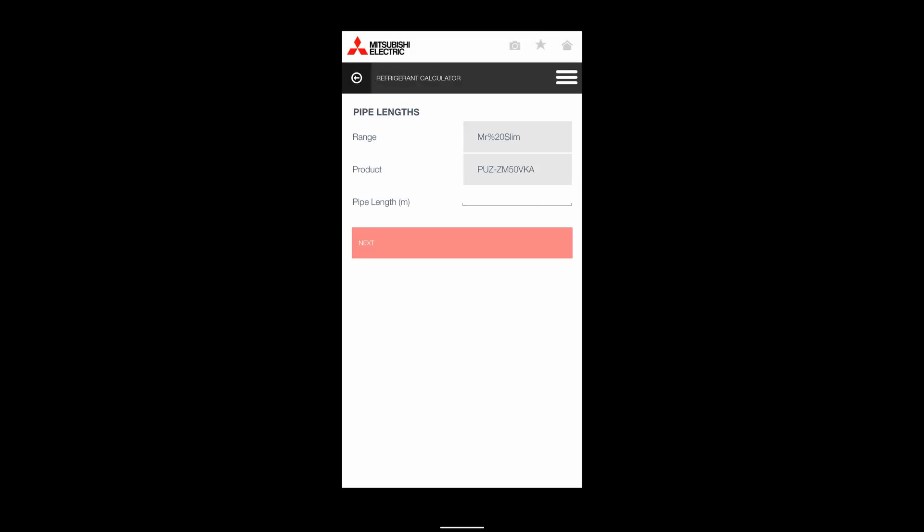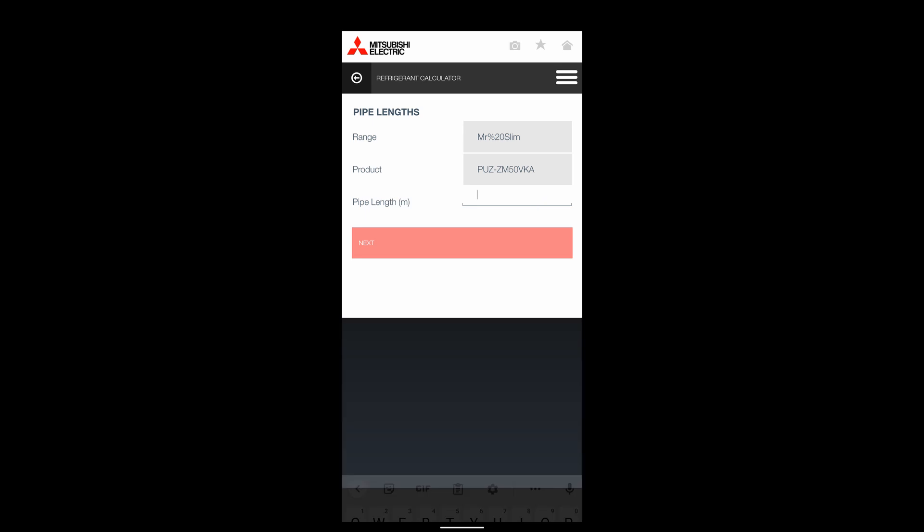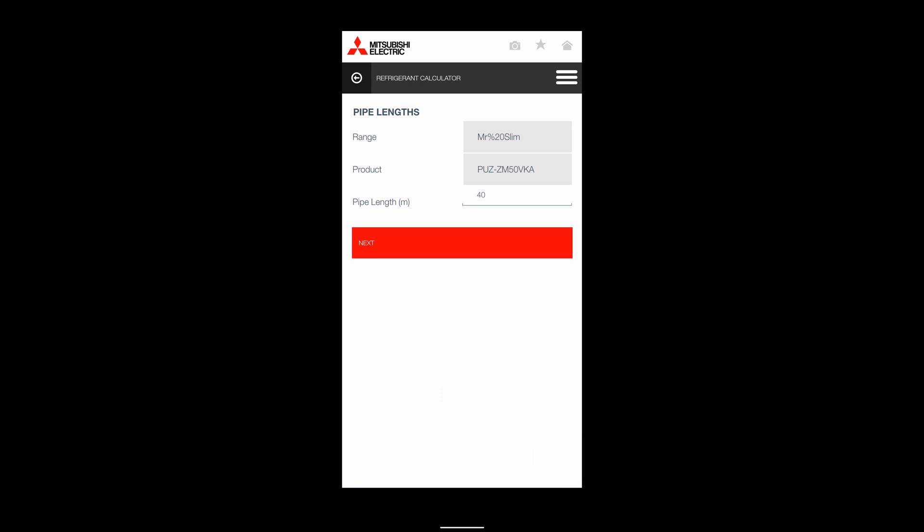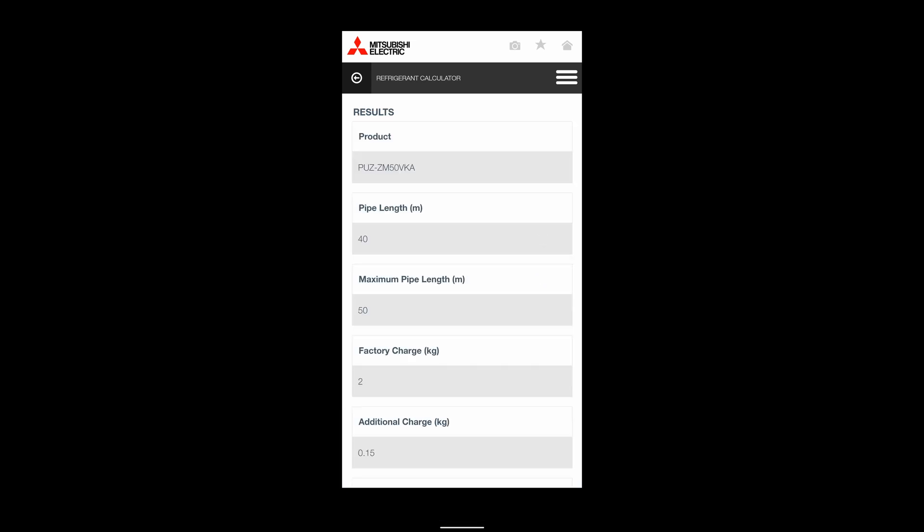We'll say we've got a pipe length of 40 meters. Now, I know that the Mr. Slim units come pre-charged for a minimum of 30 meters already, so it's going to add an additional charge.